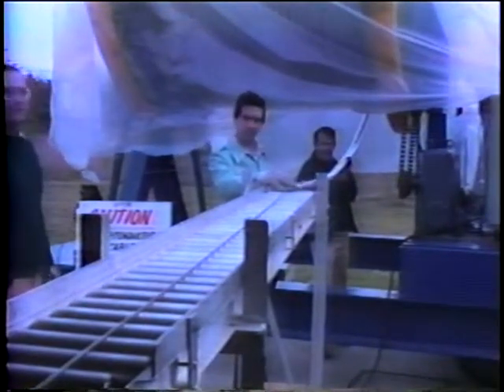With the reel in position, the cable was pulled into the enclosure pipe in 2 operations. First, about 400 feet was drawn into the pipe and the cable was cut. Then a second cable was drawn in, thus allowing a circuit to be made with 2 cables, each about 400 feet long, before final trimming.